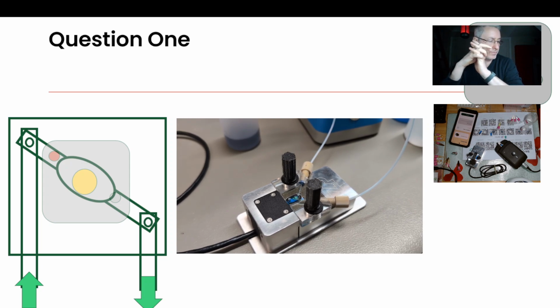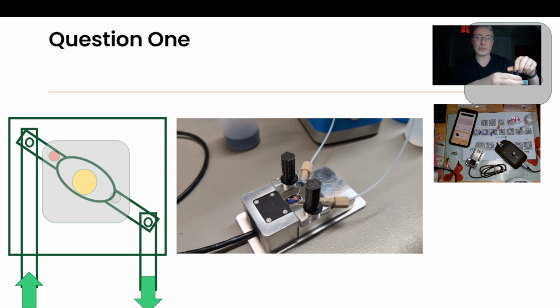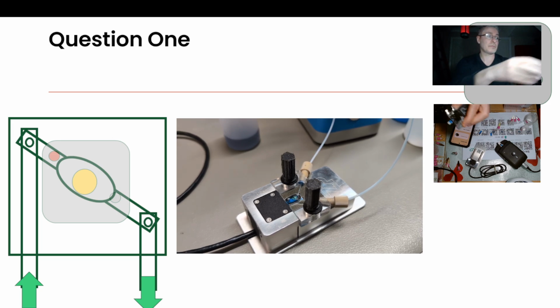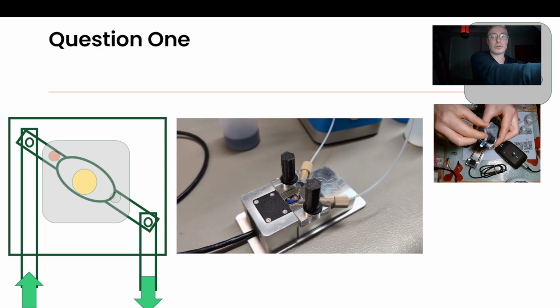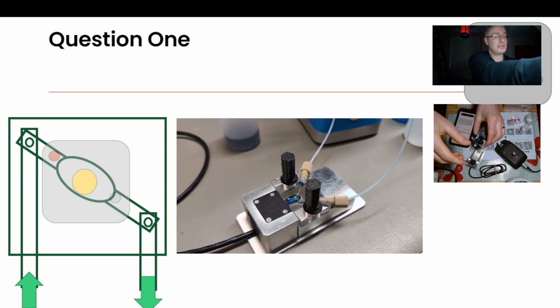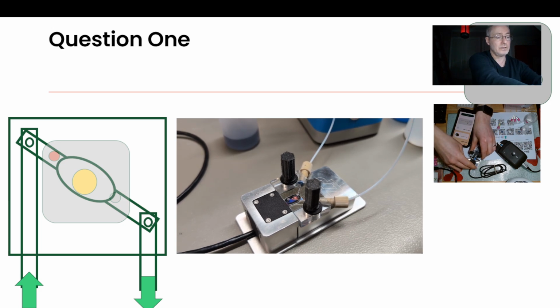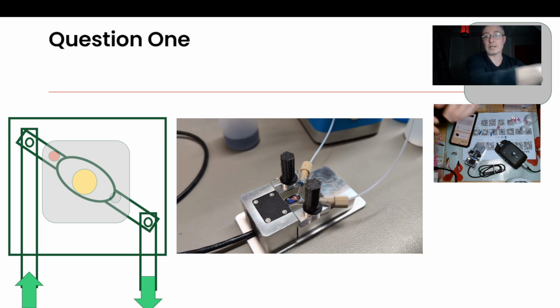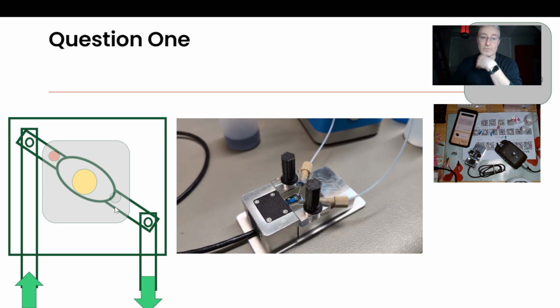With regards to flow cells for electrochemical biosensors, ZP is very experienced in it. We do contract development, contract manufacturing, including auxiliaries, or accessories rather. In fact, I'm just setting this one up now. So I've got my biosensor in there. I can then slide it into here. I can make my electrical contact here, and then I can run that as a flow cell for doing biosensing.